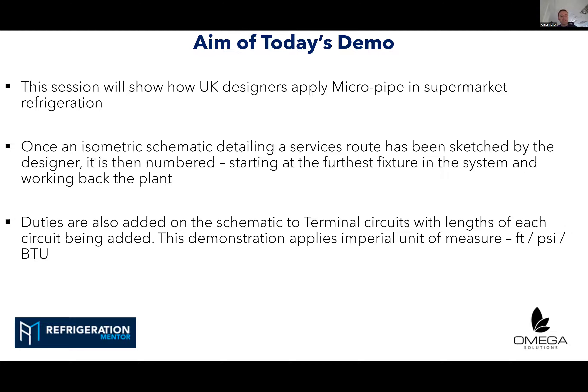This session shows how UK designers apply MicroPipe in retail supermarket refrigeration. Once an isometric schematic detailing service routes has been sketched by the designer, it is numbered starting at the furthest fixture or display case in the system, then working back towards the rack. Duties are also added to the schematic at terminal circuits, with lengths of each circuit being added. For this demonstration, I'm applying imperial units: feet, pounds per square inch, and BTUs.